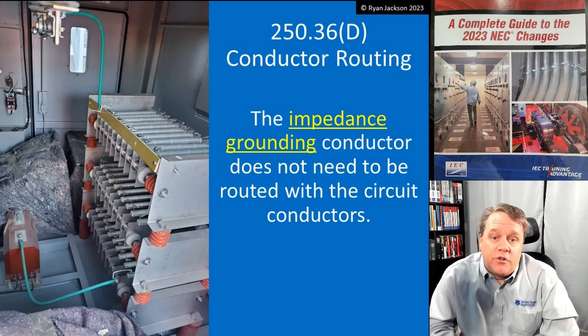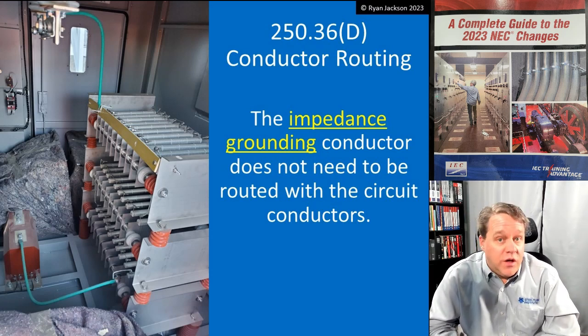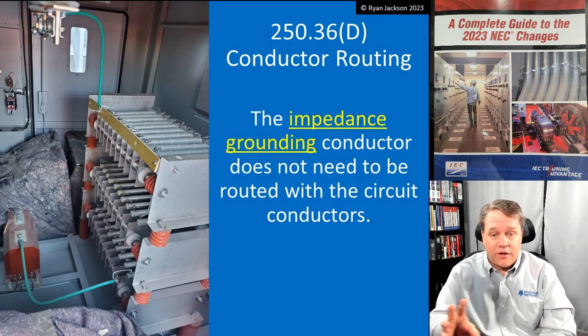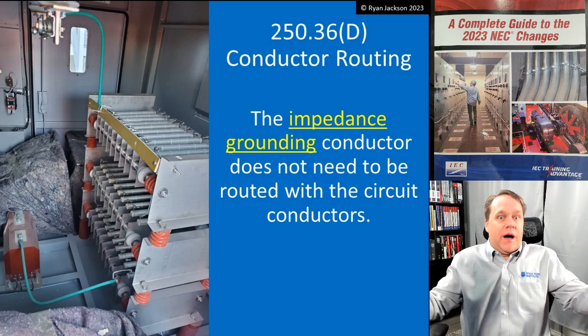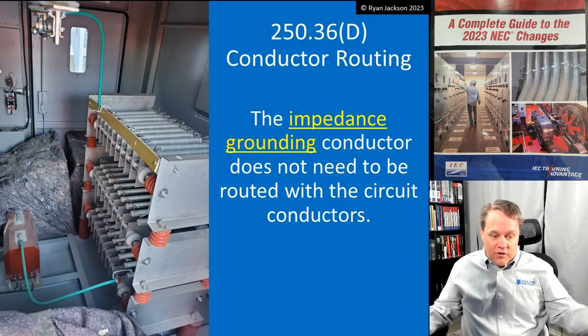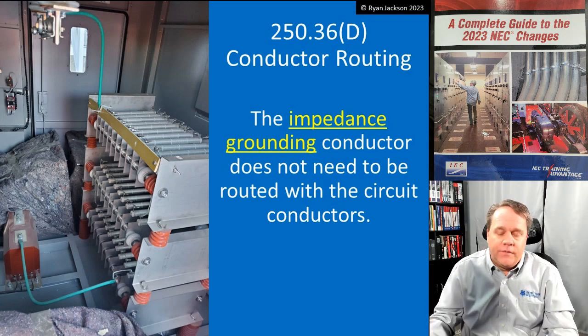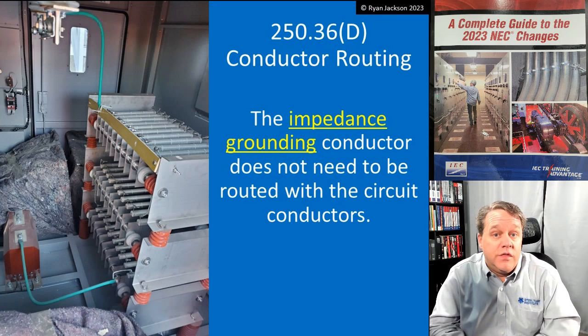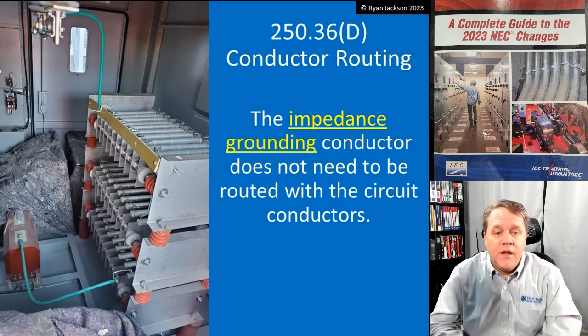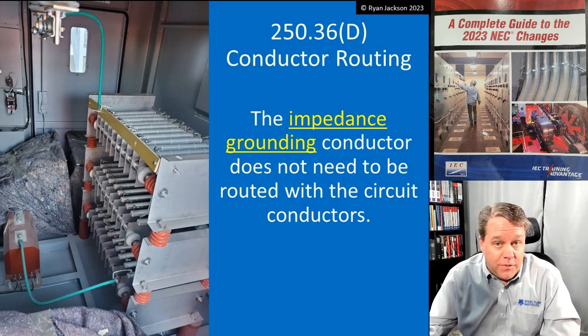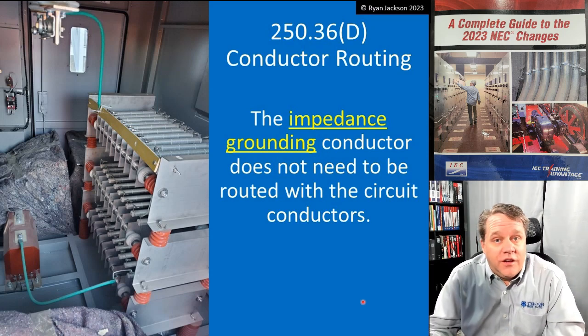The grounding impedance conductor does not need to be routed with the circuit conductors. That drives people insane the first time they see it - you've got this wire off by itself and they say, 'Wait, doesn't 300.3 say all conductors have to be grouped together?' It's fine - there's no reason to route this with the phase conductors. So there you go: 250.36 impedance grounded systems. Nice job by Code Making Panel 5 - love what you guys did on this one.